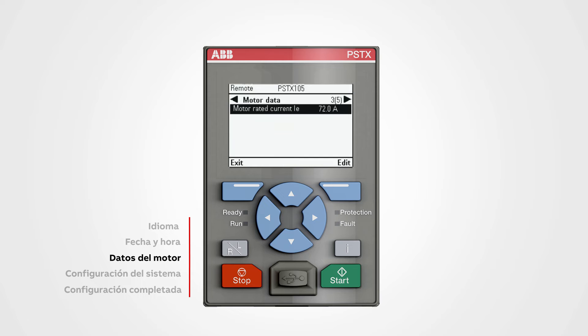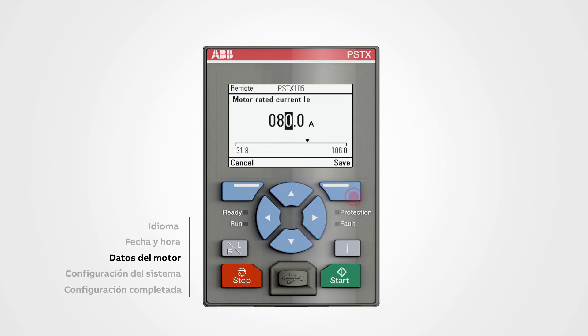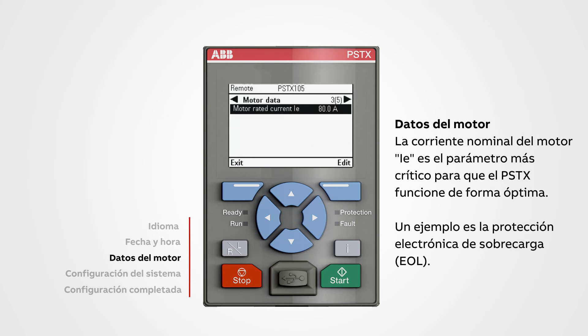Motor data: push edit to change the motor rated current Ie, then use the navigation keys to change the value and push save. Motor rated current Ie is the most critical parameter to set up correctly for PSTX to function optimally.